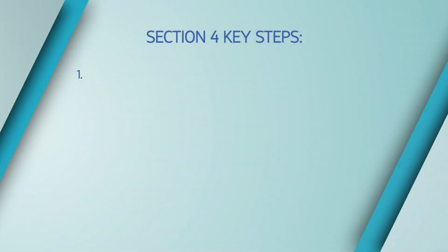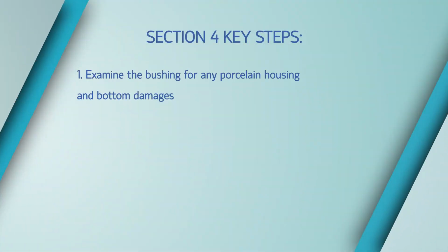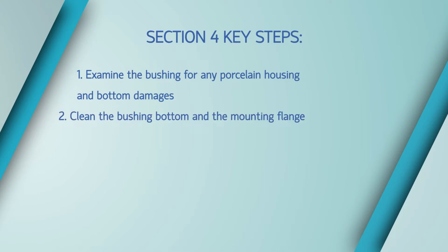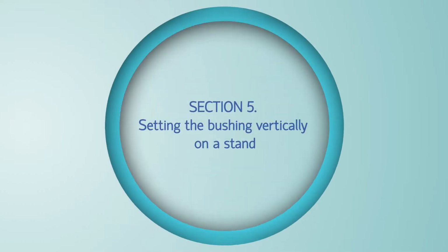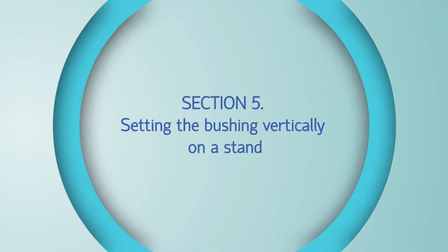Now let us follow the key steps again. Examine the bushing for any porcelain housing and bottom damages. Clean the bushing bottom and the mounting flange. Insert a rubber gasket into a mounting flange groove. Setting the bushing vertically on a stand.